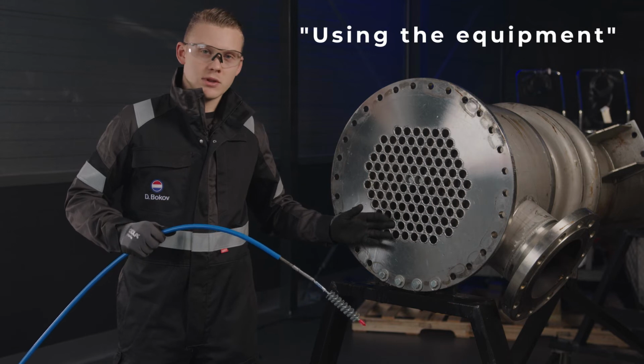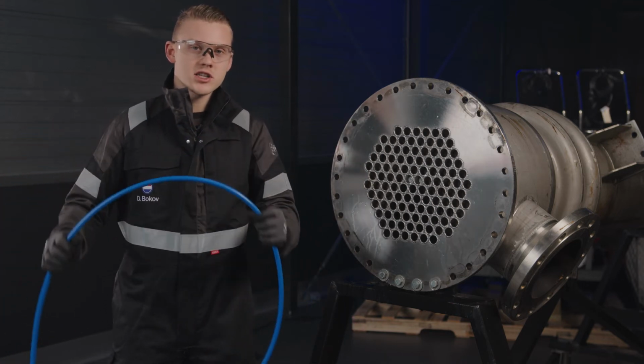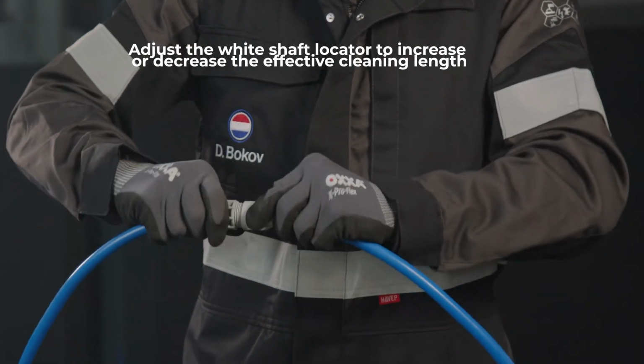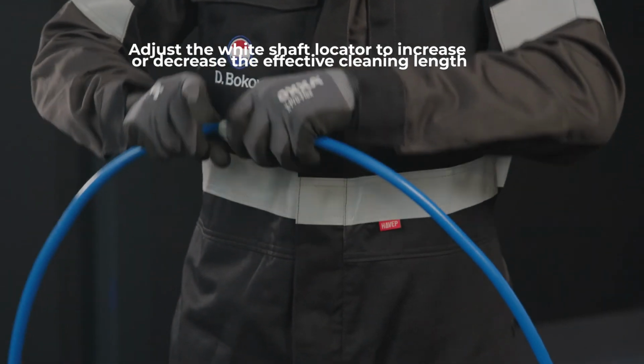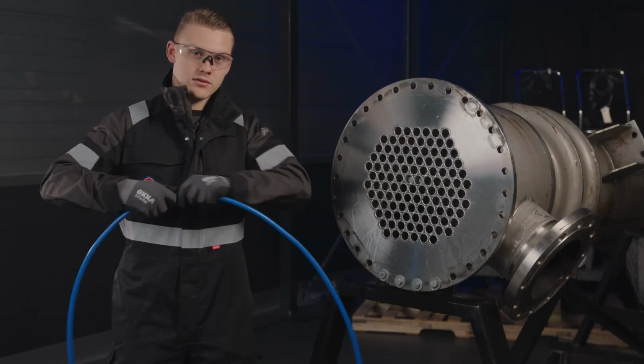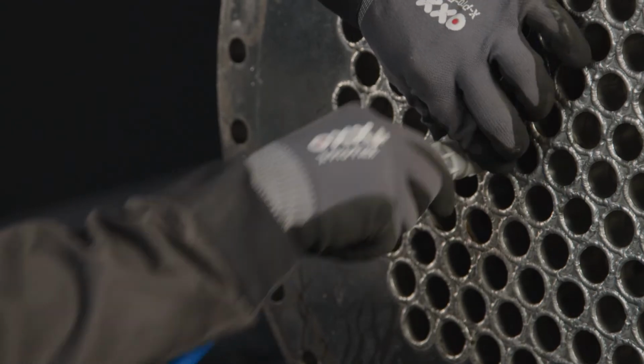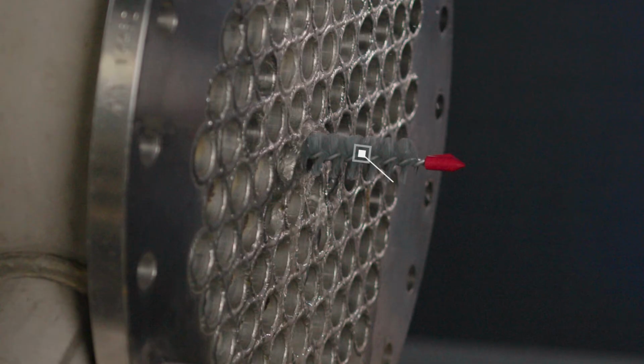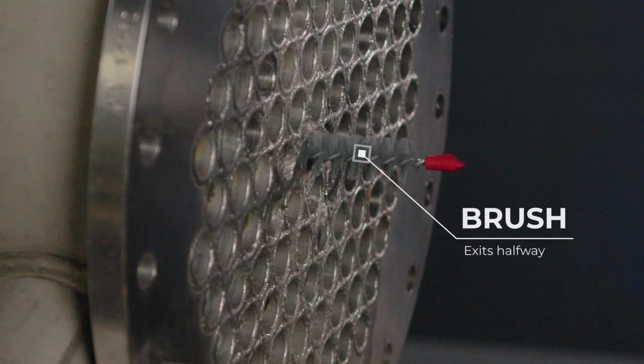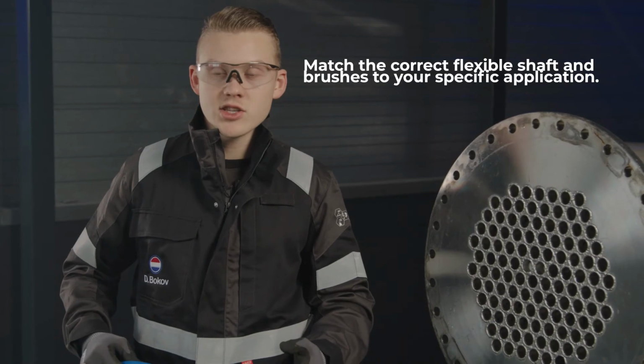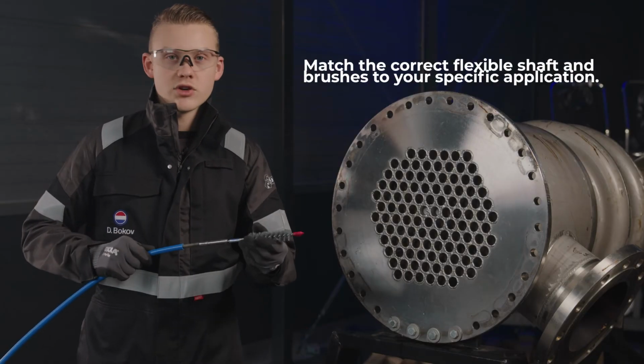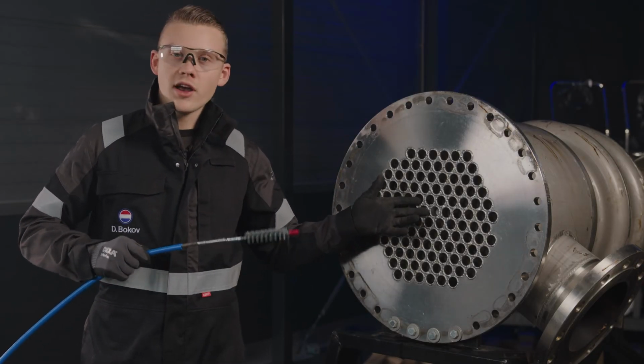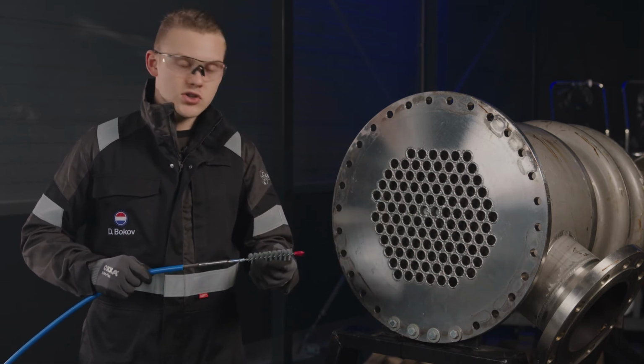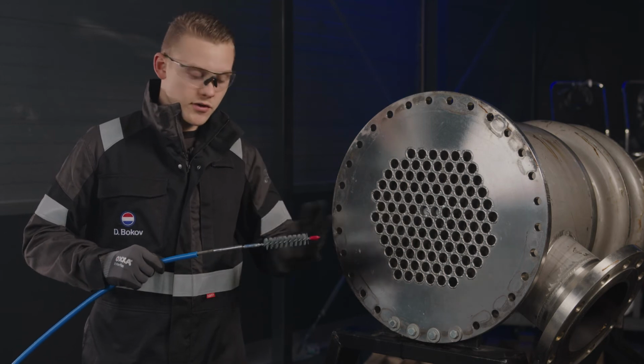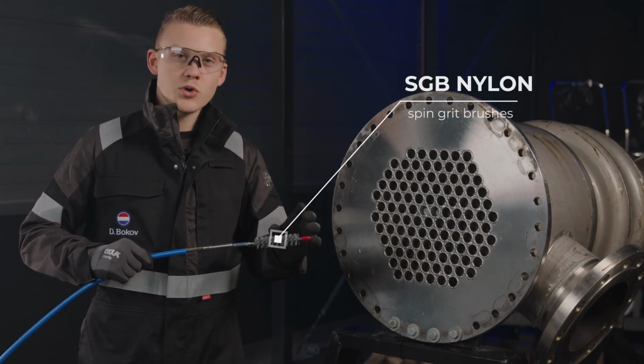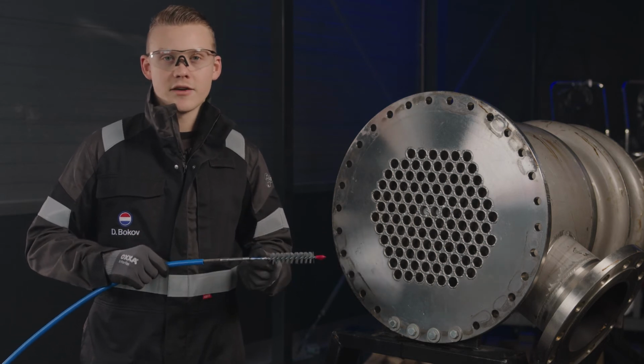Every heat exchanger has different tube lengths, therefore it is important to adjust your flexible shaft. By changing the position of this white knob, you can either shorten or lengthen the total length of the flexible shaft. It is important that the brush exits the tube halfway so you get the best cleaning effect. For this demonstration, we are using an electrical tube cleaning system with a dual switch foot pedal and quick connect brushes. Now, depending on what kind of cooler or installation you're going to clean, you may choose a different brush. For this shell and tube heat exchanger, we have used our SGB nylon brushes, which are always slightly oversized to create a better cleaning effect.